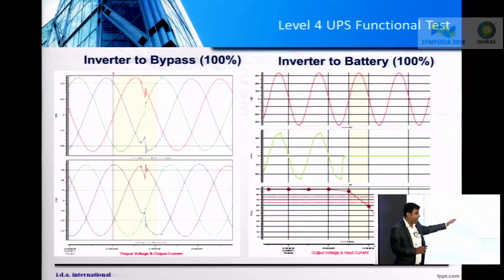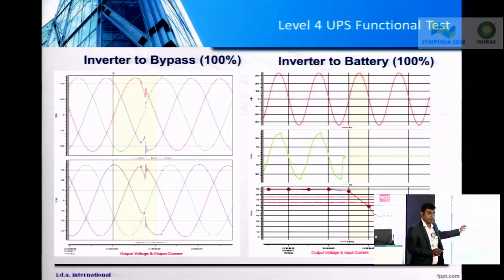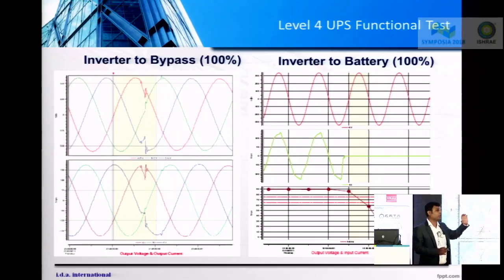Similarly, you have to verify the UPS performance when it transfers from inverter to static bypass and verify that the output voltage is intact, there is no break, there is no major distortion.